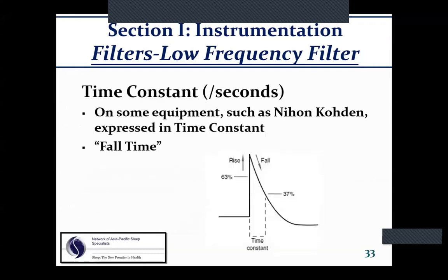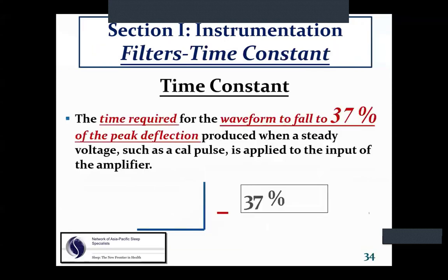So time constant on some equipment, such as Nihon Kohden, is expressed in time constant. If low filter is rise time, fall time is what time constant is. So you see that 37%. The definition of time constant is the time required for the waveform to fall to 37% of the peak deflection produced when a steady voltage, like a calibration pulse, is applied to the input of the amplifier.